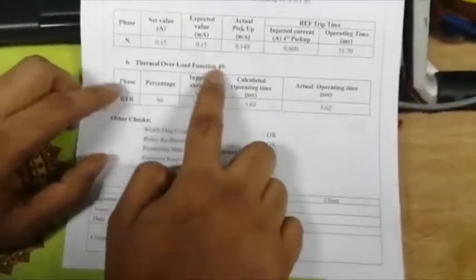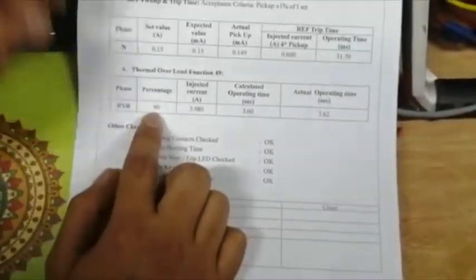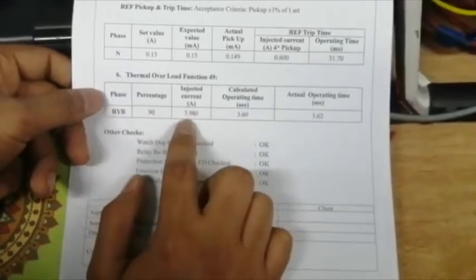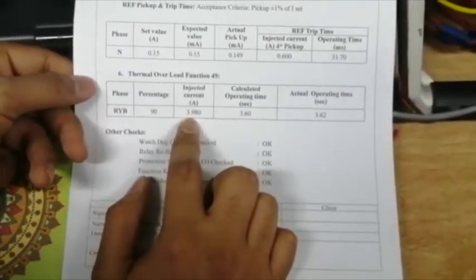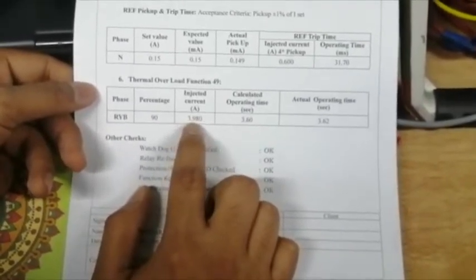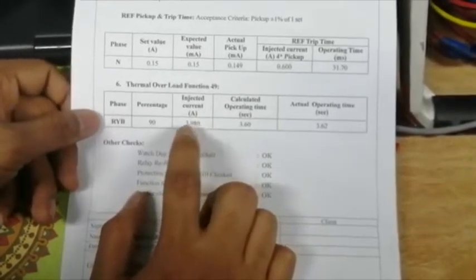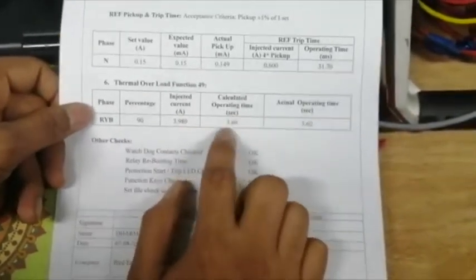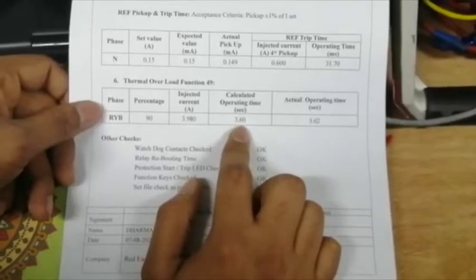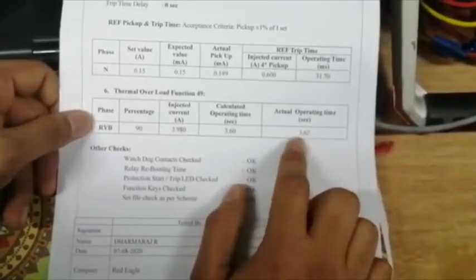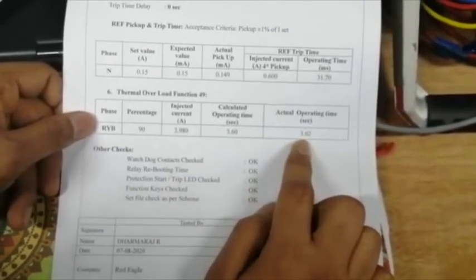Next, thermal overload protection. 90% is given in setting. My full load current is 0.996. 4 times of full load current is 3.980. For 4 times of full load current, I calculated value 3.60 seconds. I got actual trip time 3.62 pass.